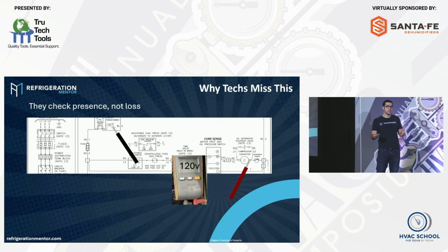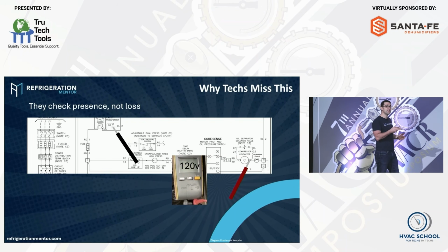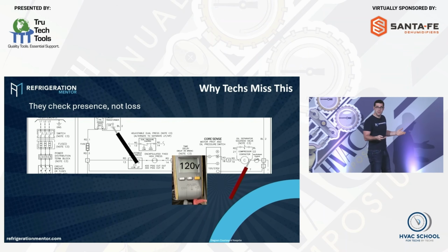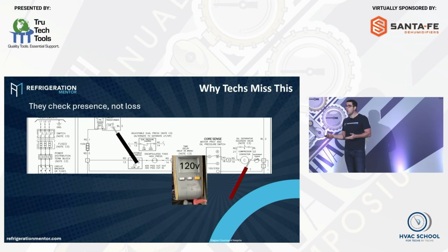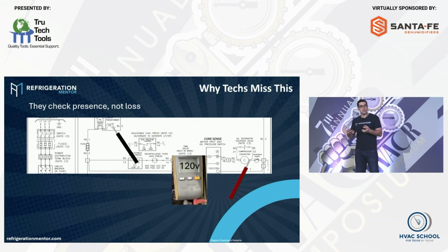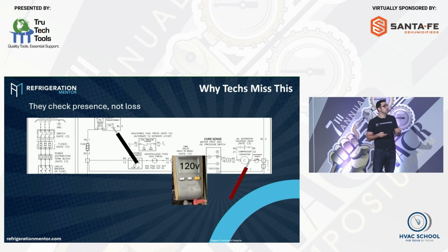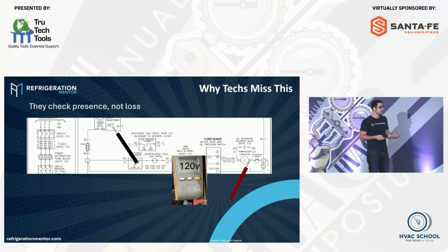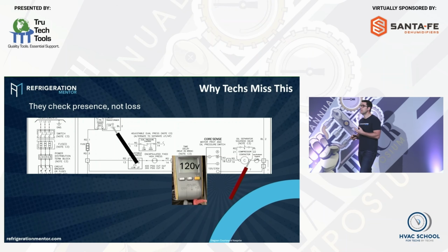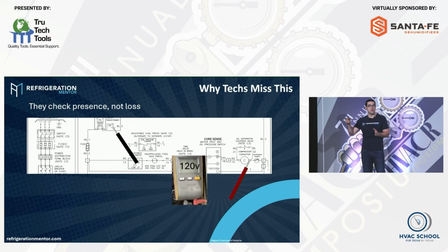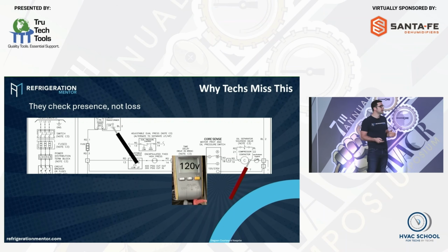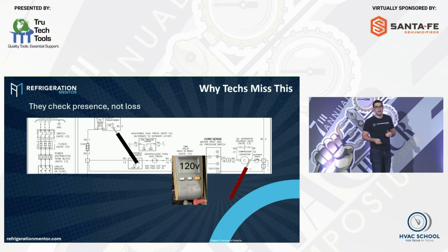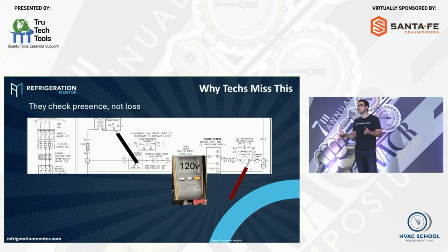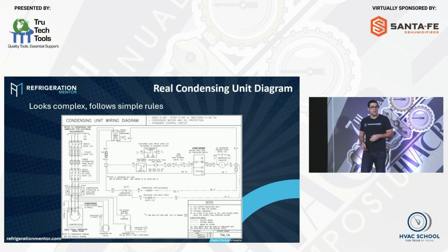Your neutral is broken, it's loose, or you have a switch in there, like a low ambient control in this example, that is open and stopping the path. Loads use the power, they need voltage, they take up power. And if we don't have it finishing in your neutral, your common, your L2 for example, then that's when it doesn't work. So this is one of the reasons why ground can lie.